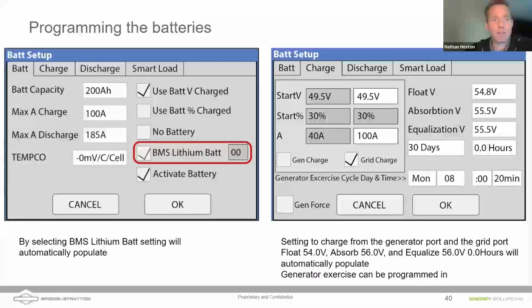Under the battery capacity, of course, on the left side of your screen, you're going to input the total number of amp hours that your battery has. You would get that from your manufacturer. In our case, we provide that to you. And the maximum charge and discharge, these are global settings where you can break this down into different sources later, but for right now, these are global settings on the left side of your screen. You see the temperature compensation coefficient on the left side of the screen is set to 0. So I think that answers your question. The answer is you can absolutely do that.